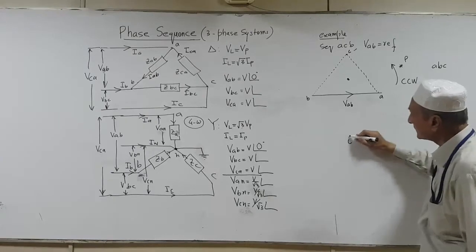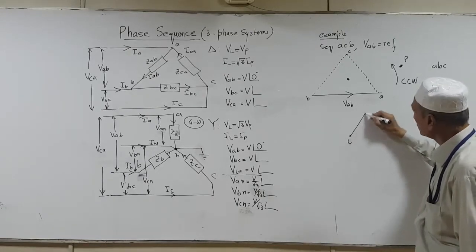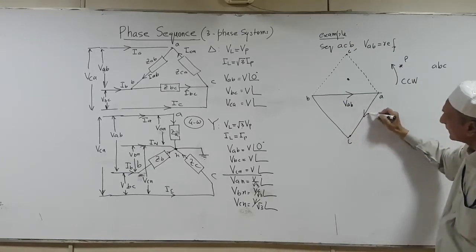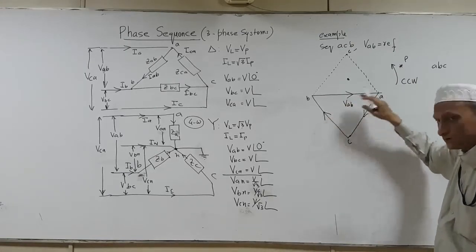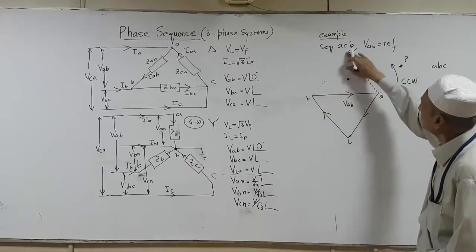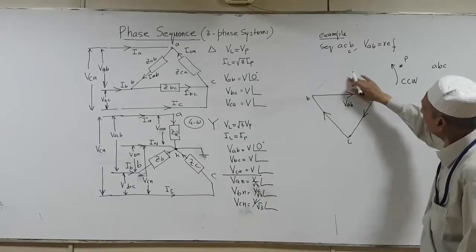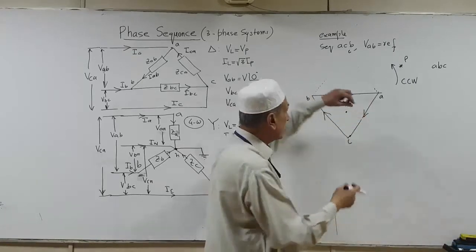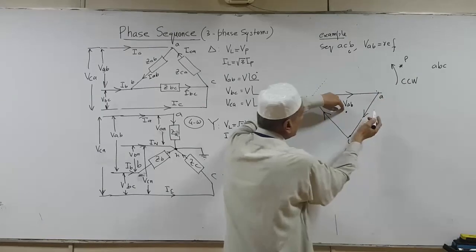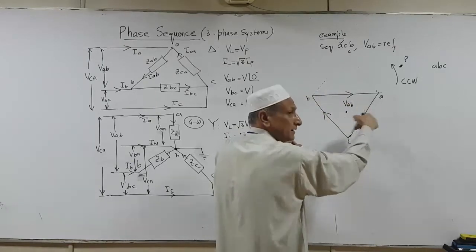Now let's consider the lower point. The lower point will do the job. So we complete the triangle and the arrows must be running. Now we could forget about the upper one and consider this one with a pivot point in the same manner and rotate this past this point P. So eventually what will happen? A will pass first, followed by C and then followed by B in rotation. So we have a sequence ACB.